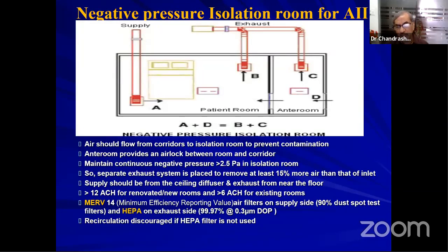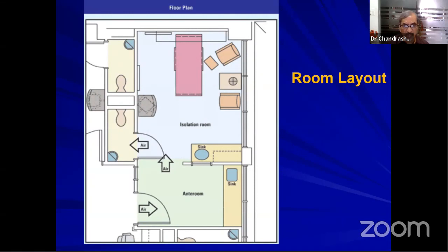Supply should be from the ceiling diffuser and exhaust from near the floor, with greater than 12 air changes for a renovated room, and a MERV 14 filter as the minimum on the supply side with a 90% dust spot test, and HEPA on the exhaust side. Recirculation is discouraged if a HEPA filter is not used. And generally nowadays, even in tier 2, tier 3 cities, when this becomes a challenge, we throw the air through a sodium hypochlorite solution tank also, so that at least the air we throw out is neutralized.